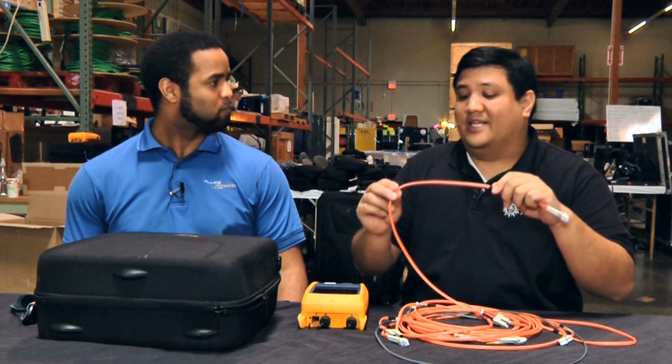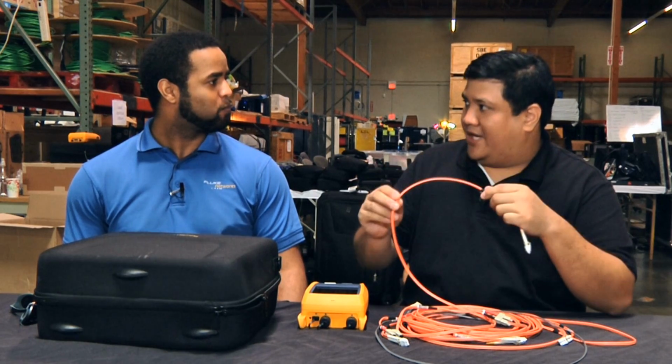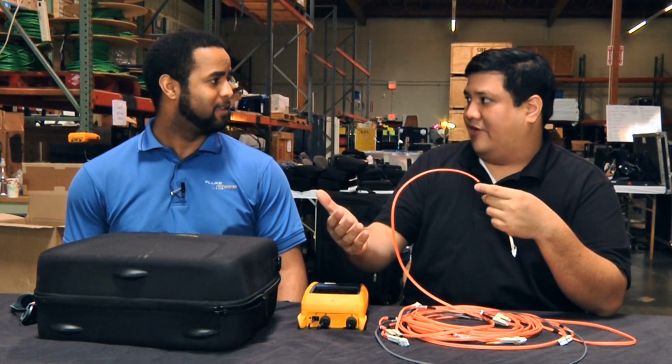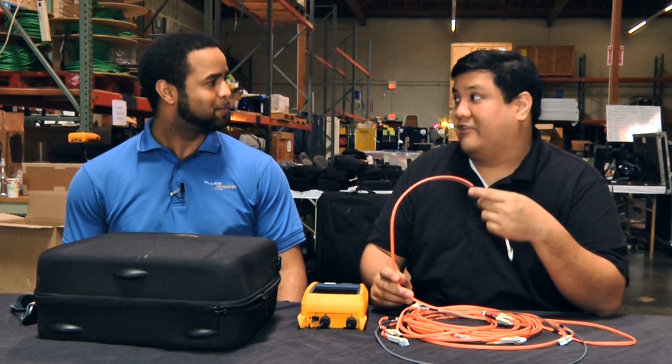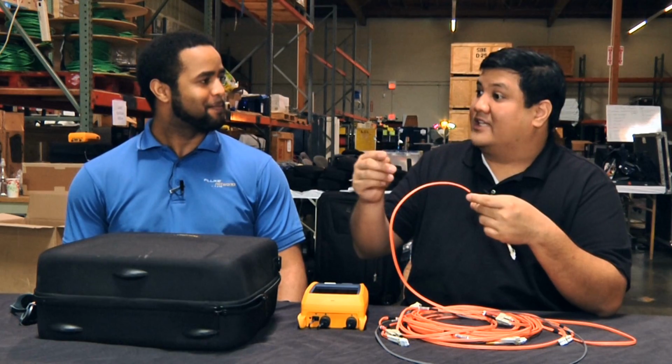Right. Another big advantage of using OTDR equipment is that I can tell if there's a break. Yes. For example, if I know I have a 300-meter run of fiber, and my OTDR equipment is telling me I've only seen 100 meters of fiber here, you know that somewhere along the line, at 100 meters, you've got something wrong with your fiber plant. Yes, and that can be very helpful for long runs of fiber, but it can also be very helpful in a data center environment.